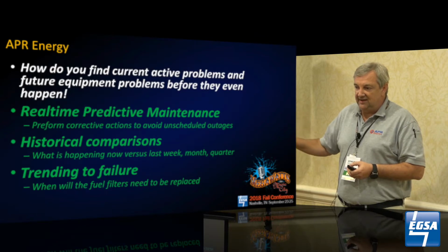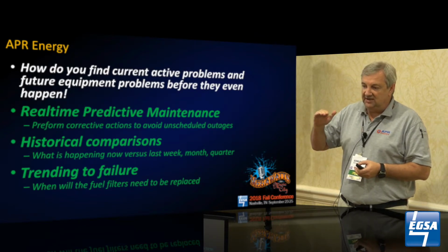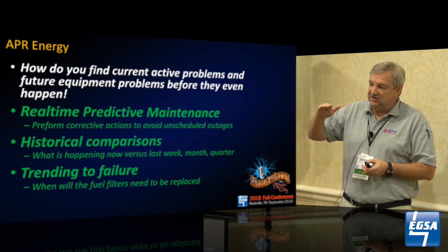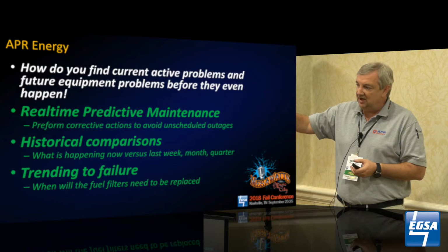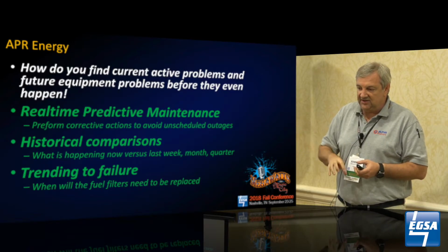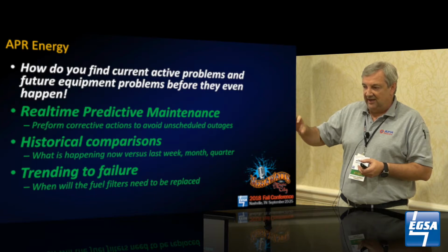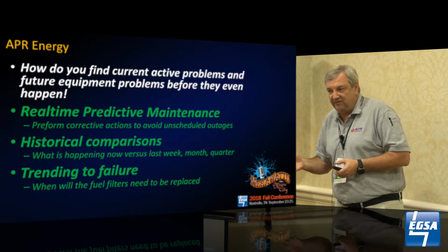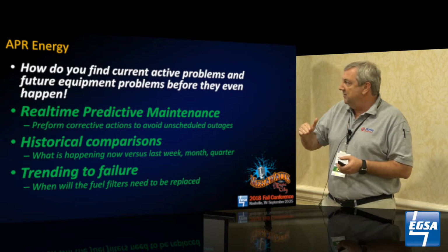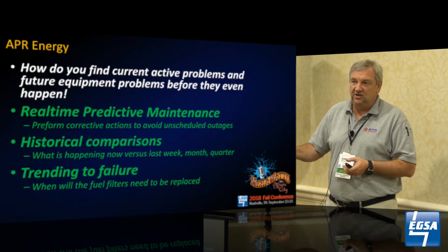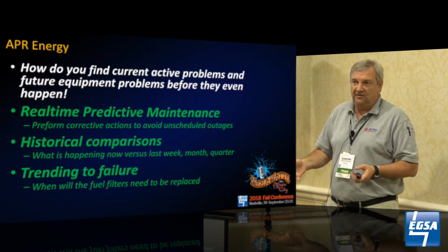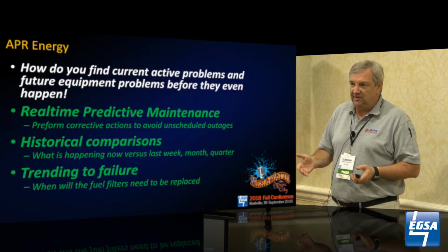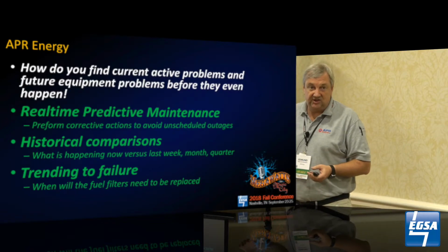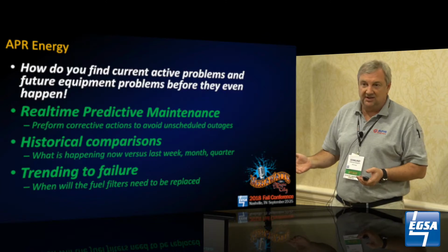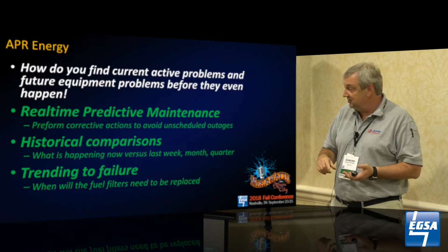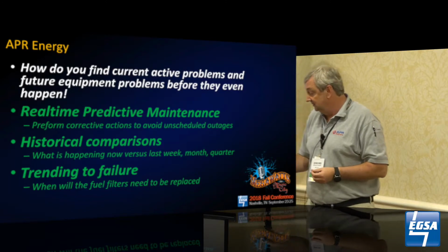Using analytics again and looking at predictive data, the delta P on my air filters is slowly increasing because they're getting clogged up. Is that unique in one area of the site - too much dust? Or is it internal in the genset - oil coming off the engine and clogging the air filters? We want to predict that and do a scheduled outage on the engine at my convenience. The maintenance staff can go out, do the service work, bring the engine back up, and we're not waiting for air filters to fail and get ingested by the turbocharger, now I've got a major costly event - engine down, blown turbochargers, and I'm not generating money off the asset.